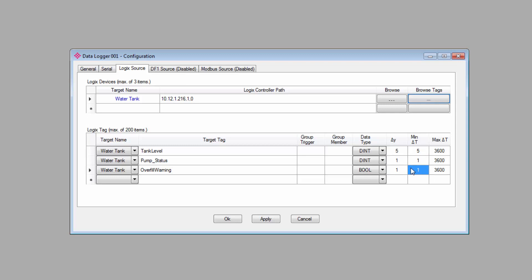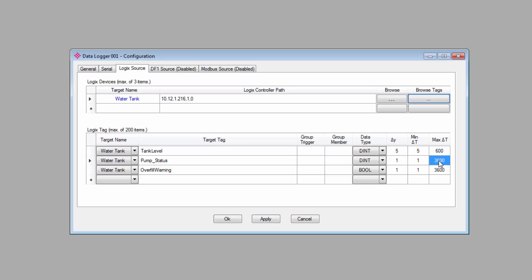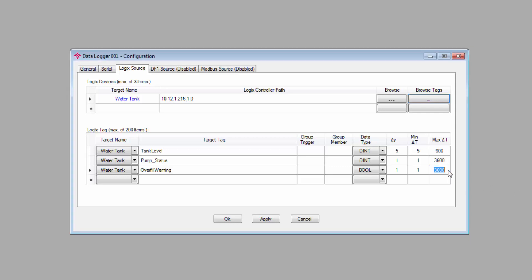The final parameter here is the maximum time between logs. By default, we have it set to 3600 seconds or 1 hour, at which time it will log the data for the tag even if nothing is changed. Again, you can configure this to log data with the frequency that you think you'll need for the variables that you're monitoring. For my tank level, I'll set a maximum time of 600 to log the value every 10 minutes. And for the other two, I'll just leave it at 3600 since I don't anticipate them changing very often.